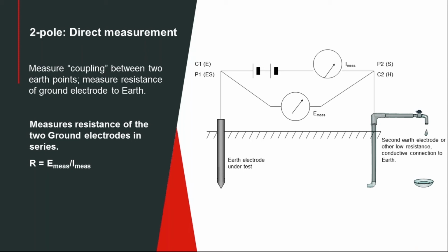And then you're going to run a lead out to some convenient return point. What is very often used in this situation would be the water pipe system, because it's pervasive and it's metal, so it should contribute relatively little to your reading. The idea is when you energize the tester, the test current is going to travel through the soil over to the water pipe system and then return through your leads. It's going to tell the tester what the series loop resistance of that entire loop is. And what you're relying on is that the soil around your electrode is what's contributing nearly all of that number.